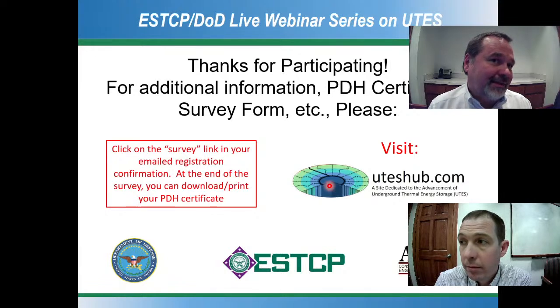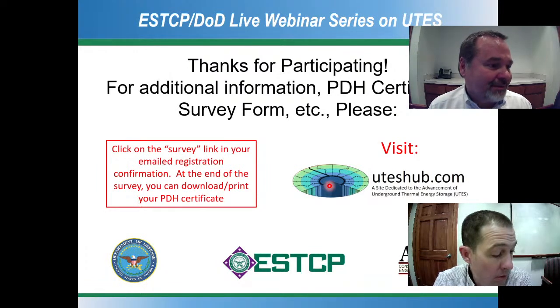So I think for geothermal heat pumps with heat recovery, unless you're in a hospital or something with a big base load, you need the geothermal to keep the heat recovery chillers stable. And even then, you need the factory people there, and you need a commissioning agent like Brandon that cares and sits in there and works that sequence to death until you get those chillers behaving. You got any comments on how to make those chillers behave?